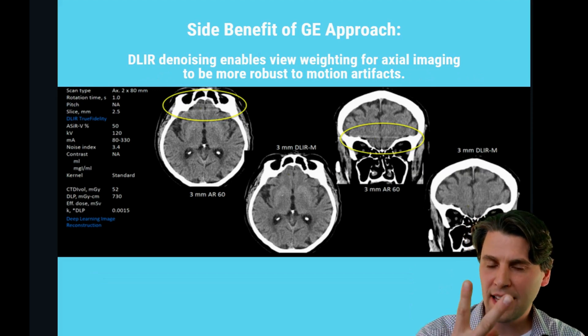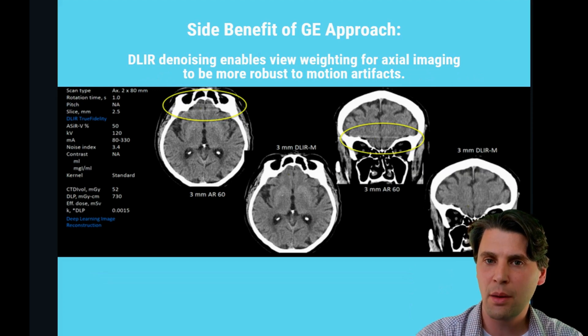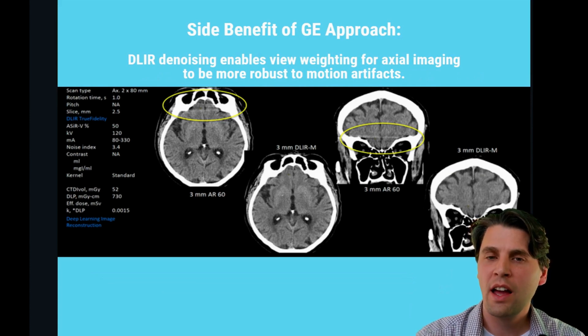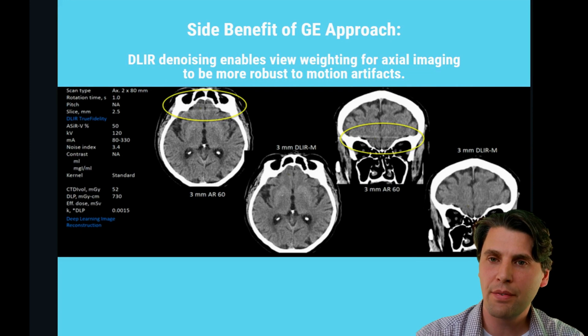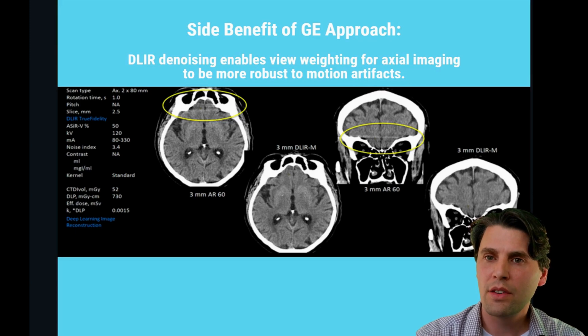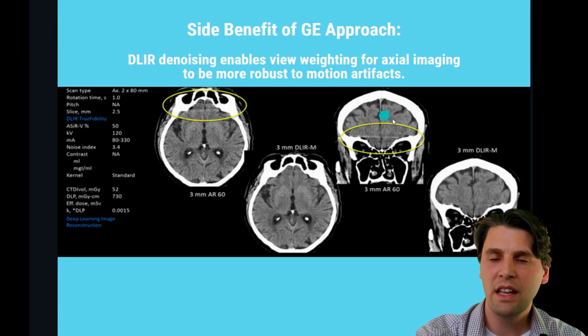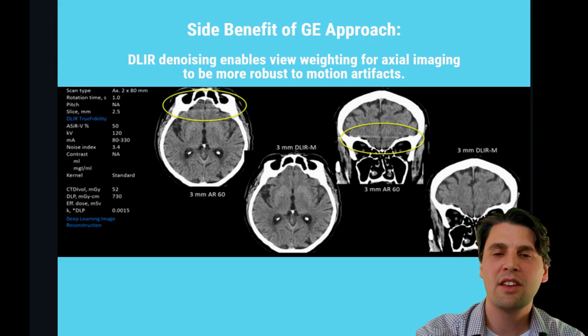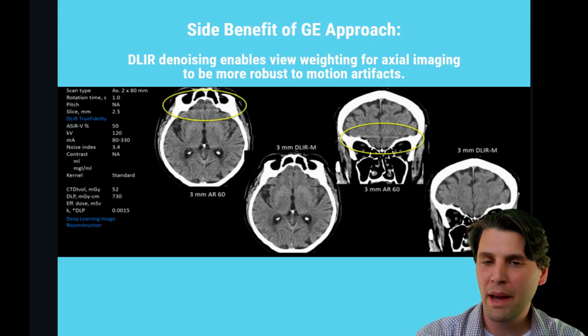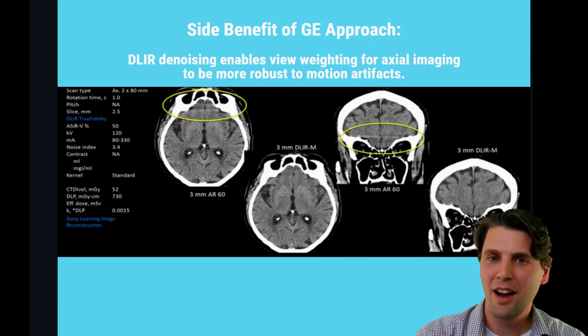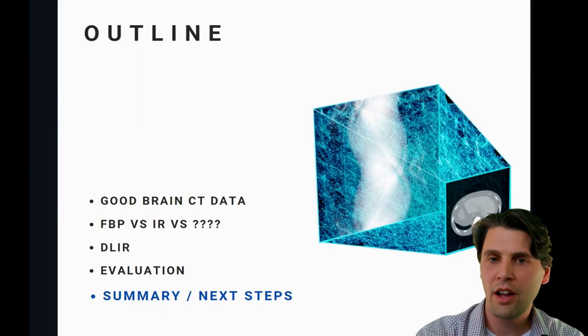A second area of interest, in addition to thin slice imaging, is axial imaging. With DLIR we get a reduction in noise as a side benefit, and we can use that noise reduction to modify the view weighting on the system to achieve significant improvements in motion artifacts — going from this type of image to this type of image. This was in fact the first case of our medical evaluation; it wasn't a cherry-picked case, just the first one off the shelf. You can see there is significant improvement, and that's another area of clinical interest.